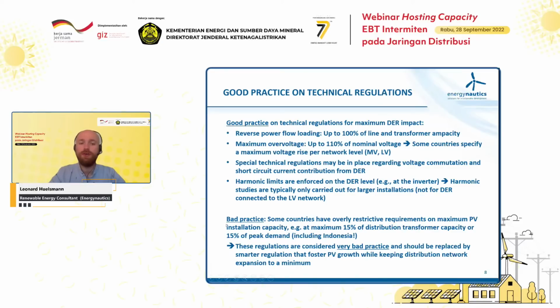You would also have certain requirements in terms of how much overvoltage would be allowed—usually for most countries this is 110% of nominal voltage. You may also have special regulations for dealing with voltage commutation or short circuit current contribution from distributed generators, as well as specifying harmonic limits.